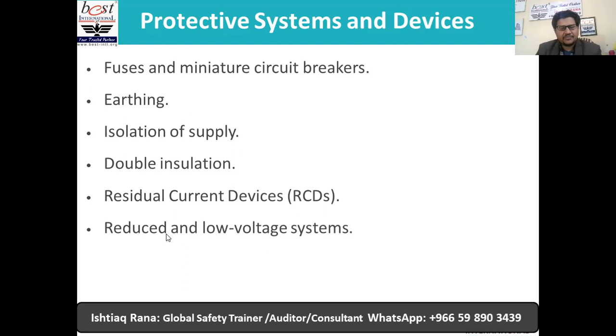Now, protective systems and devices: fuses and miniature circuit breakers, earthing, isolation of supply, double insulation, residual current devices, and reduced and low voltage systems. We also have GFCI, ground fault circuit interrupter, for 110V electric power tools. For 220V or above, we can use RCD, residual current devices, and reduced and low voltage systems.